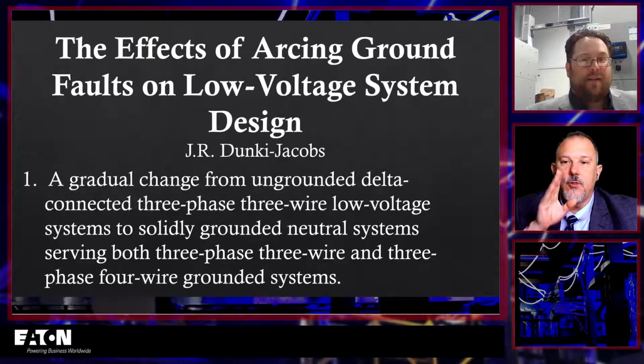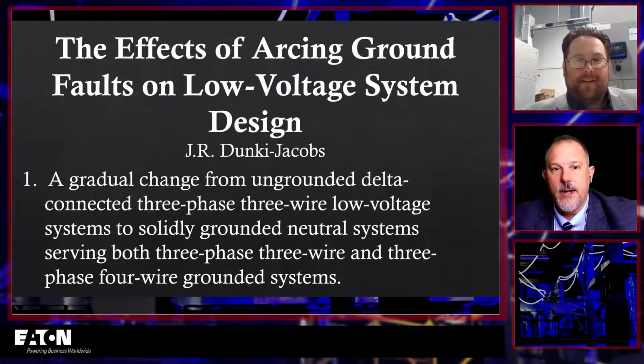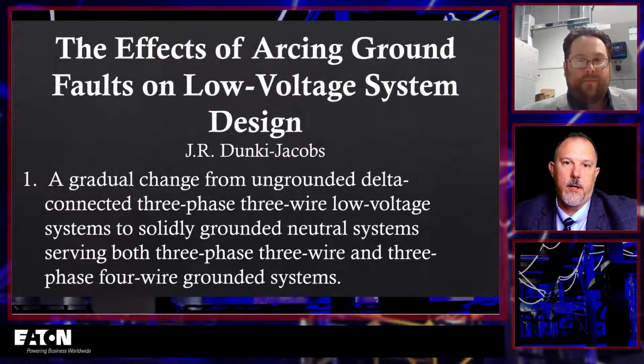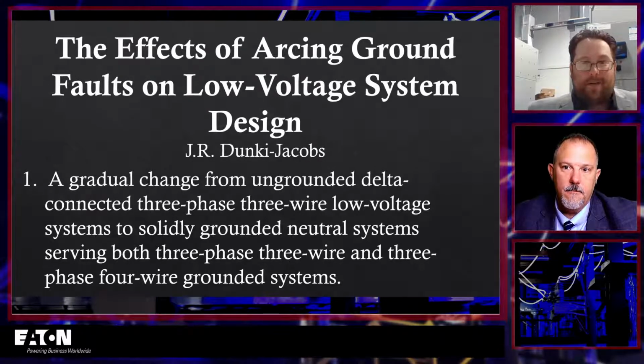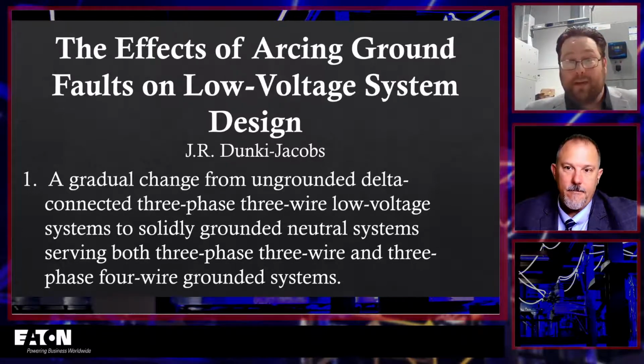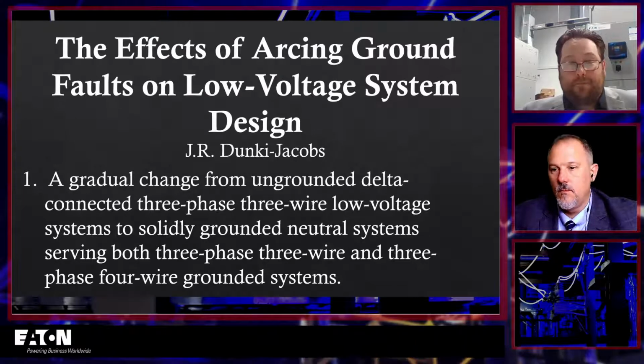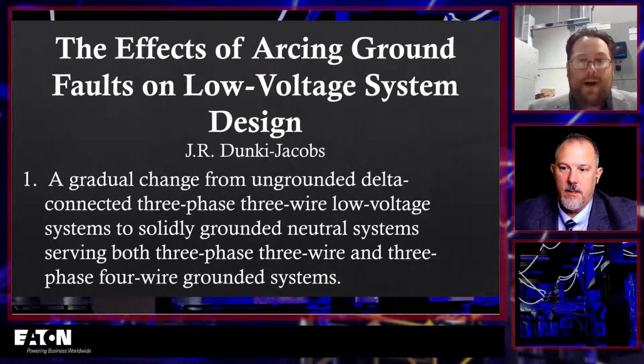Michael, can you tell us what are some of the issues with ungrounded systems? Why would I not want an ungrounded system? Any ideas? Well, ultimately, if you have a true ungrounded system and you have a fault occur, you're going to energize your equipment essentially at that phase voltage, right? I mean, that's a possibility. Yep. Ultimately that means you have that shock hazard that the users of electrical equipment are now exposed to.